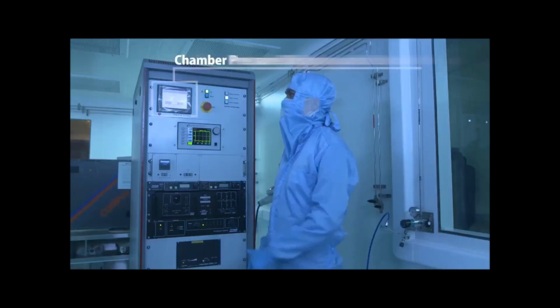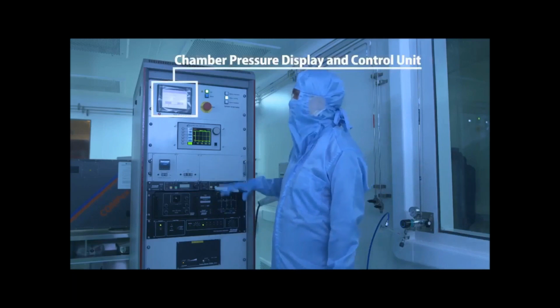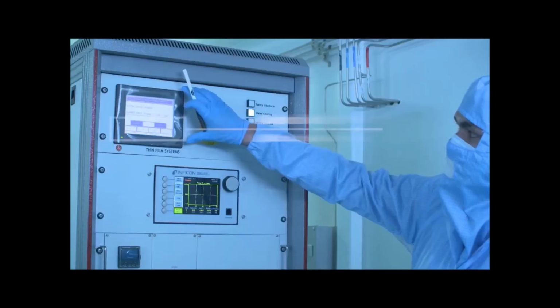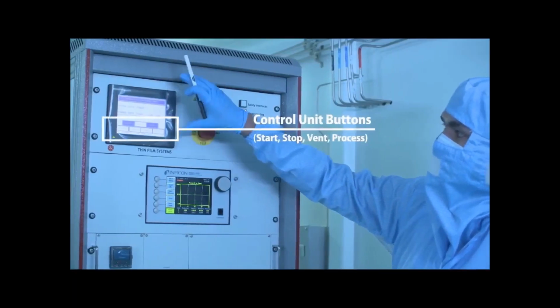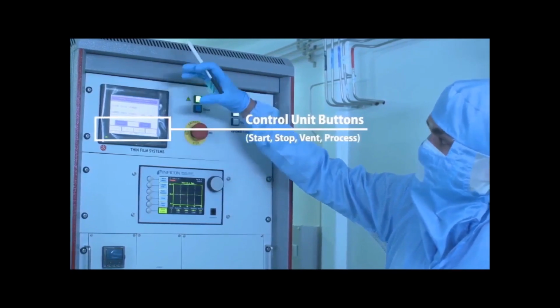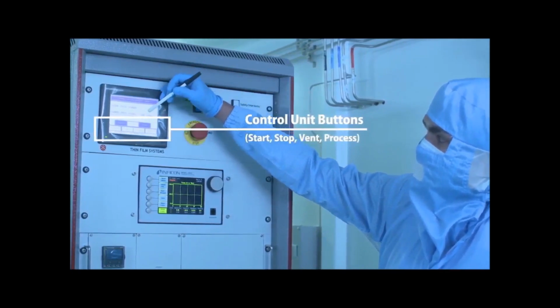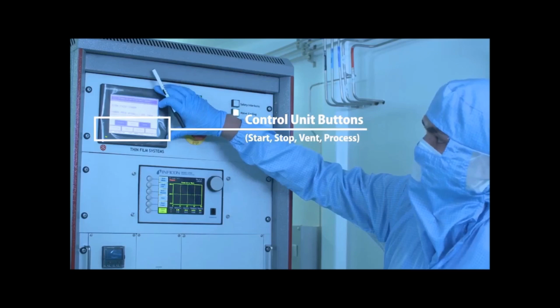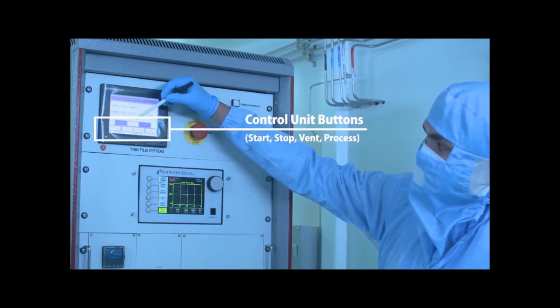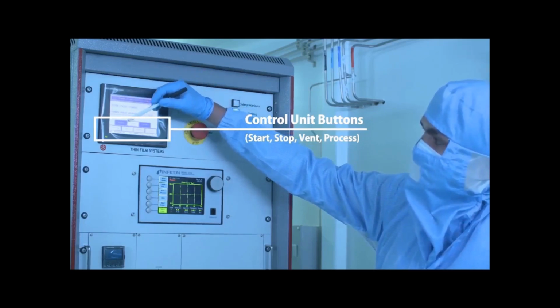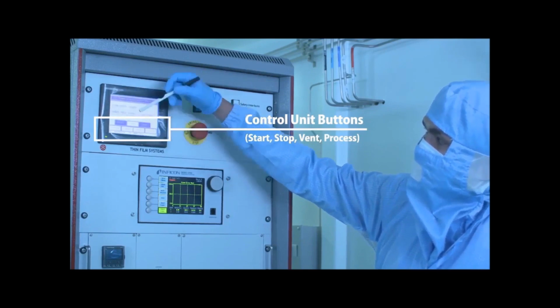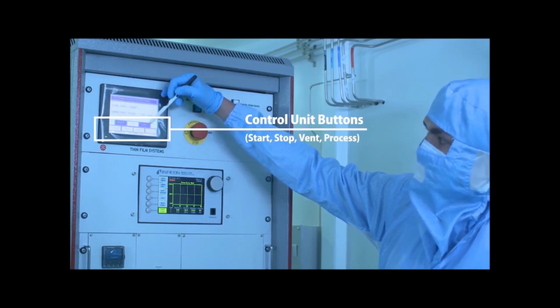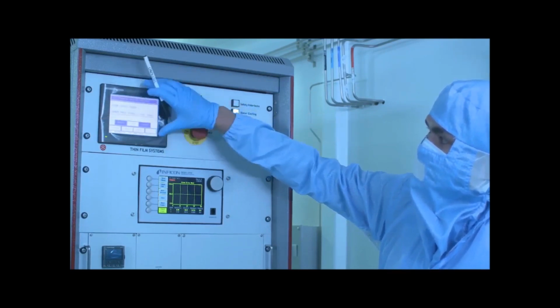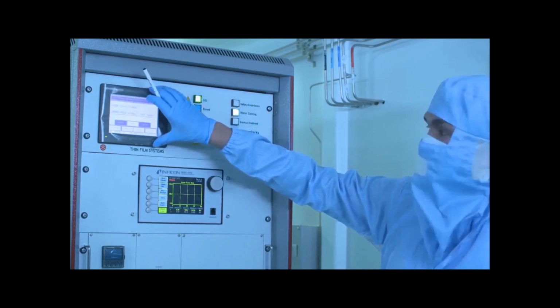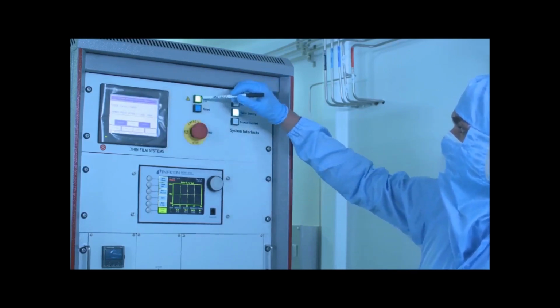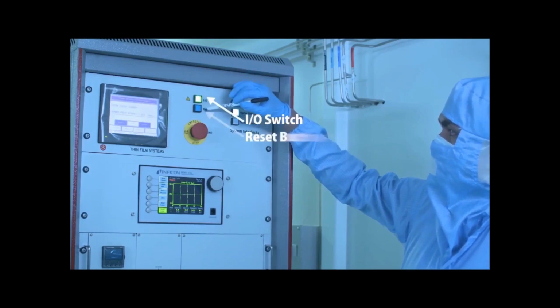Now let's try to understand the different components of our control unit. First is the display. This displays the chamber pressure, and as you see here, it shows the chamber pressure in millibar inside the deposition chamber. It also has many touch buttons, and this is used to start the process, vent the system, and the whole deposition process can be started from this unit.